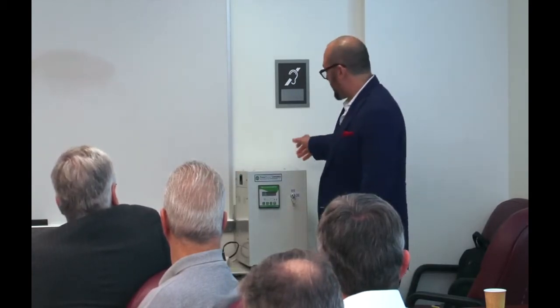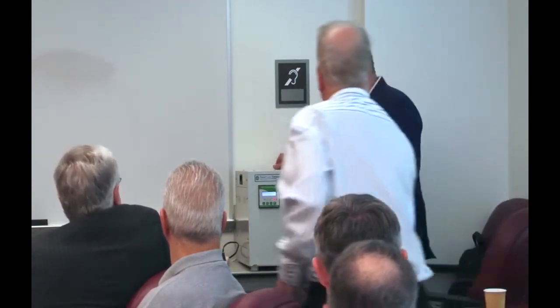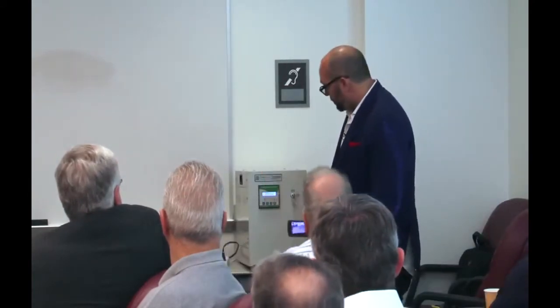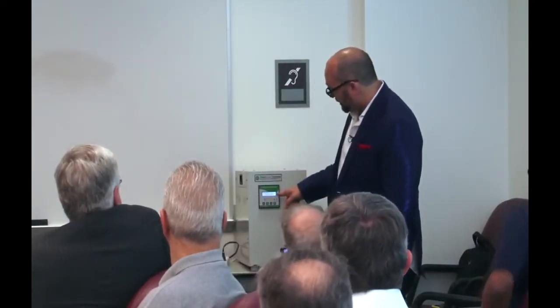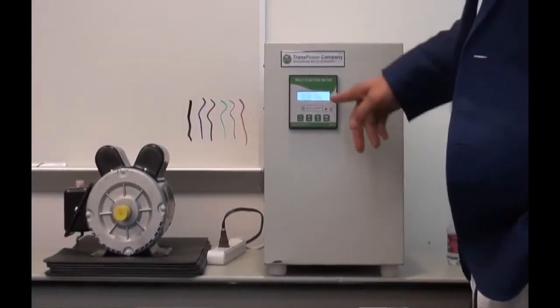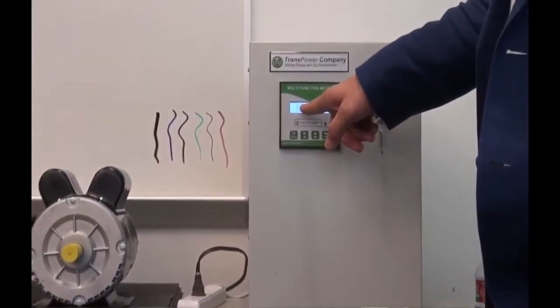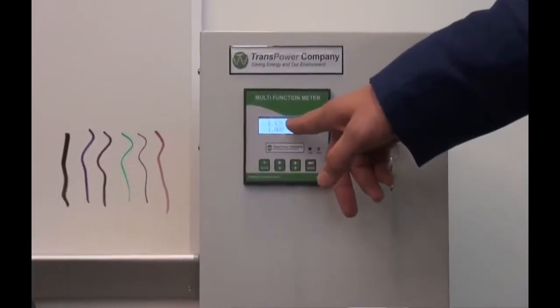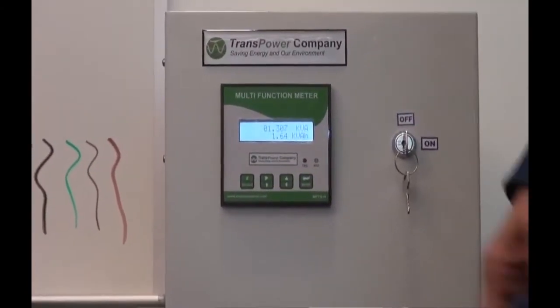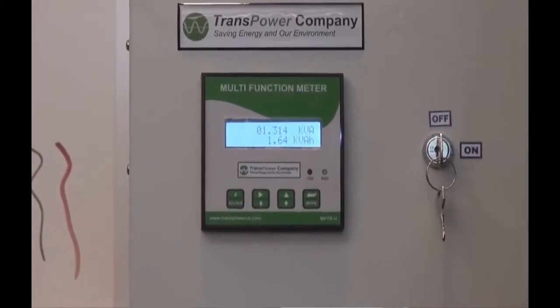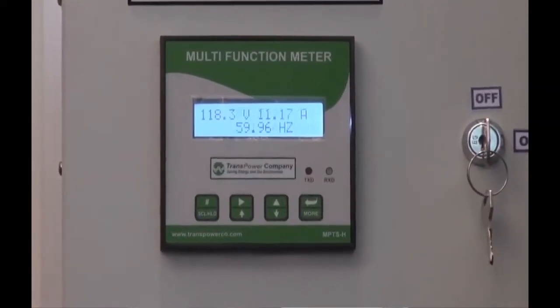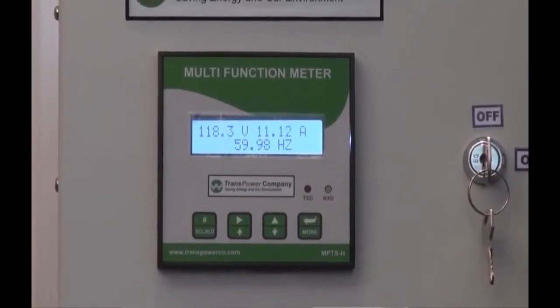So as I begin to turn on the breaker, we start to see the numbers come up. It's pushing 11 amps, which is pretty standard—between 10 and 14 is what we see. The power factor is at 0.42. The kVAR is at about 1.0, and the kVA is at 1.3. So we still haven't turned our equipment on as of yet.